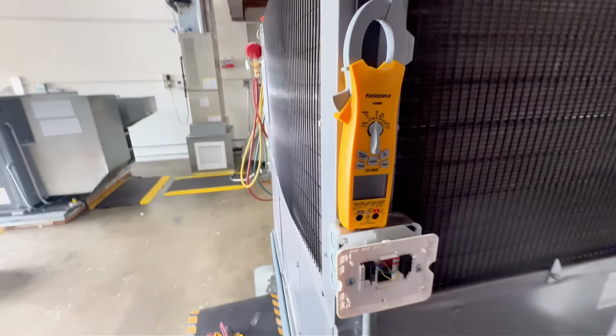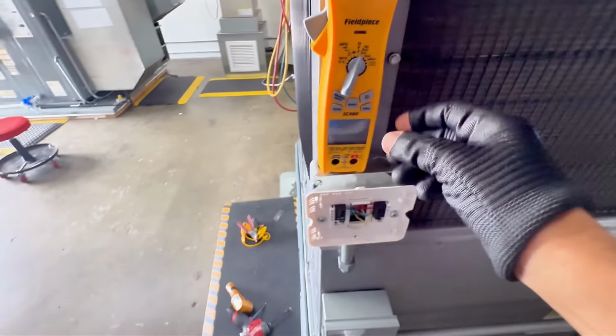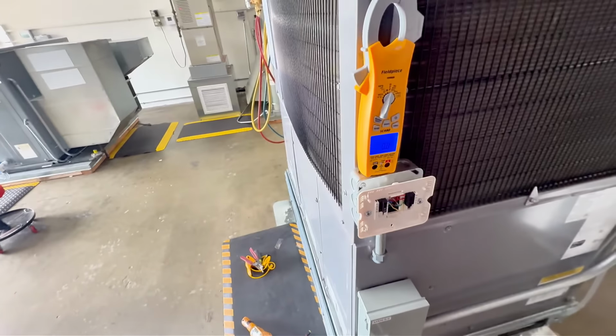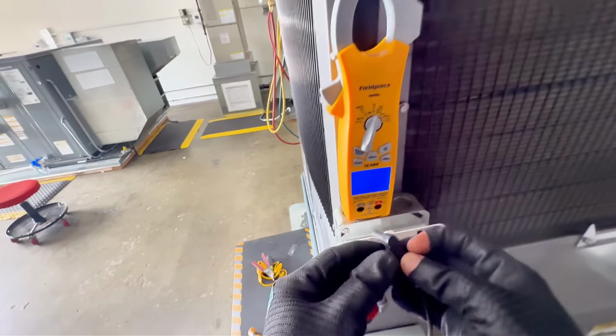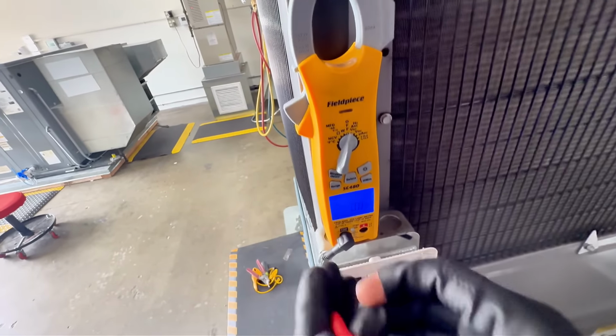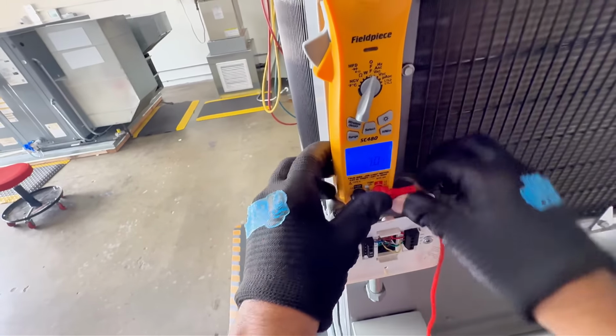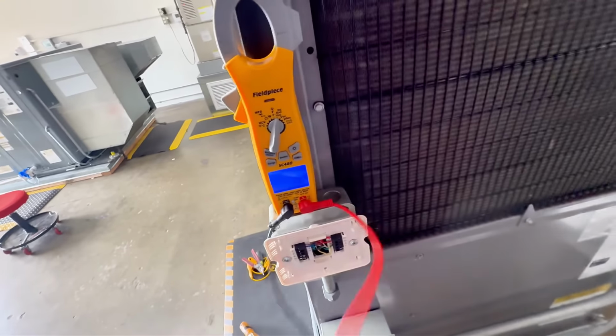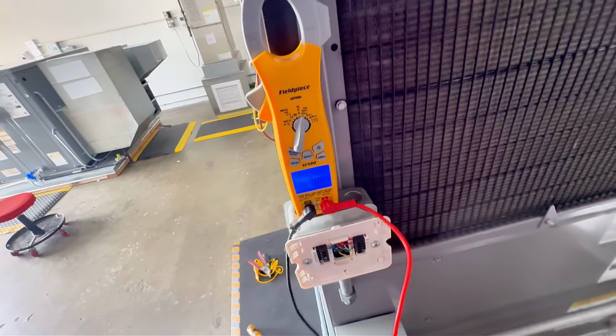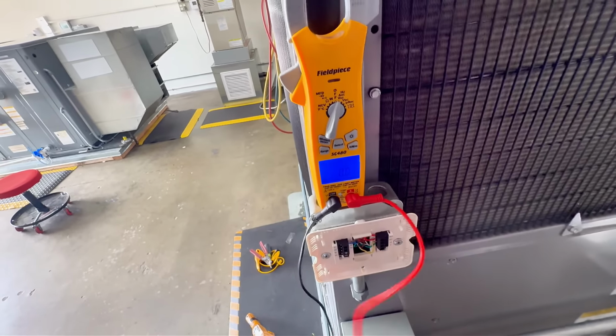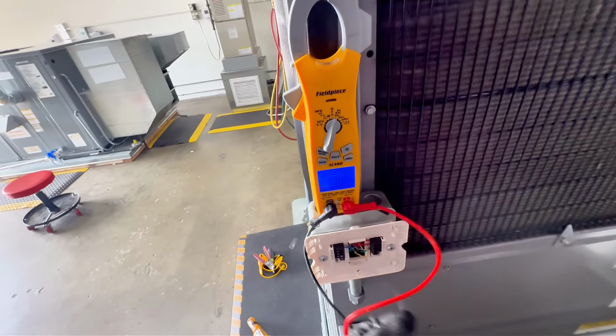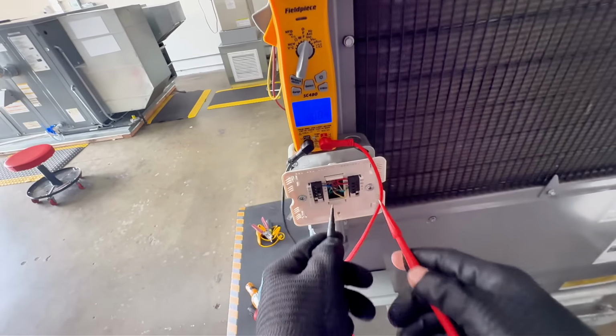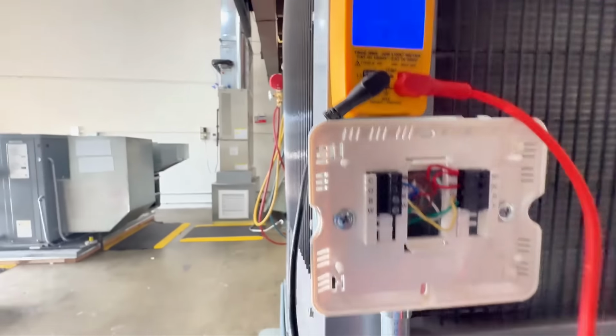So let's go ahead and put it on volts. This is the first thing that you would do: check the thermostat, right? I check the thermostat first. This is after asking questions, finding out what's going on with Mrs. Applebottom. But we're gonna have 24 volts going to that because our thermostat was on. And I said earlier, I don't know what the issue is, but I'm gonna check now. Let's go ahead and check.